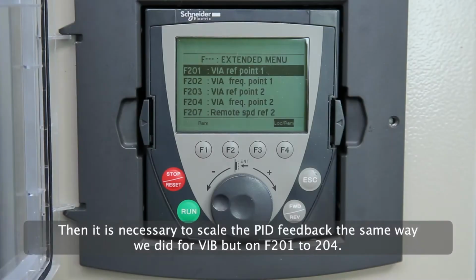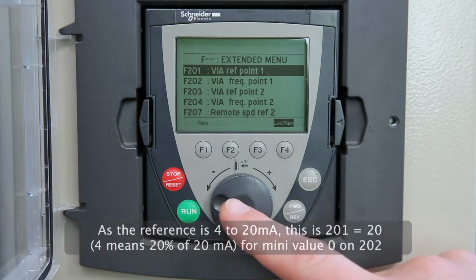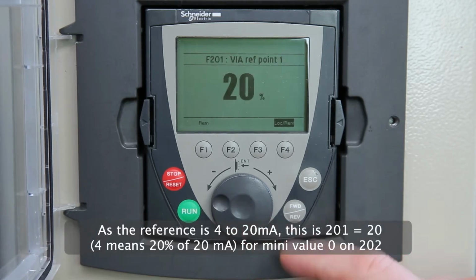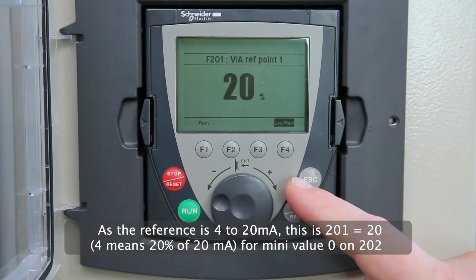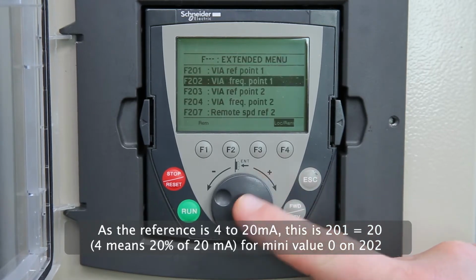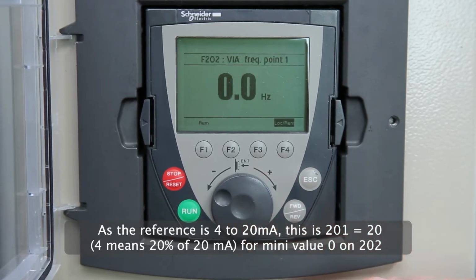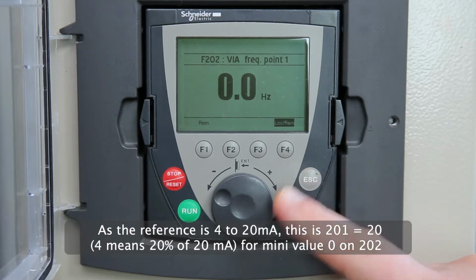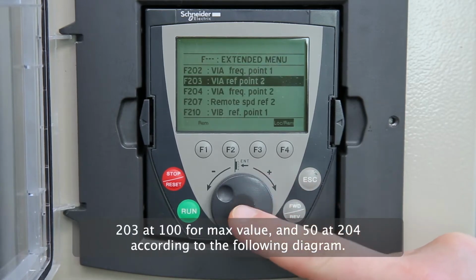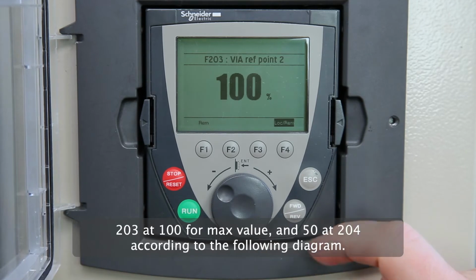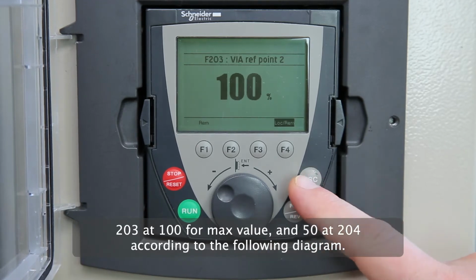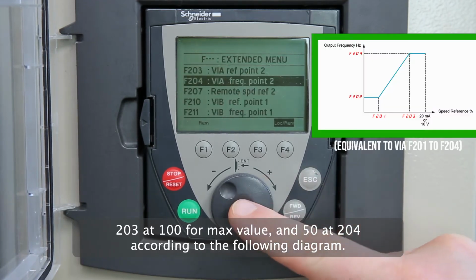Then it is necessary to scale the PID feedback the same way we did for VIB, but on F201 to F204. As the reference is 4 to 20 milliampere, this is F201 equals 20, for min value 0 on F202, F203 at 100 for max value, and 50 at F204 according to the following diagram.